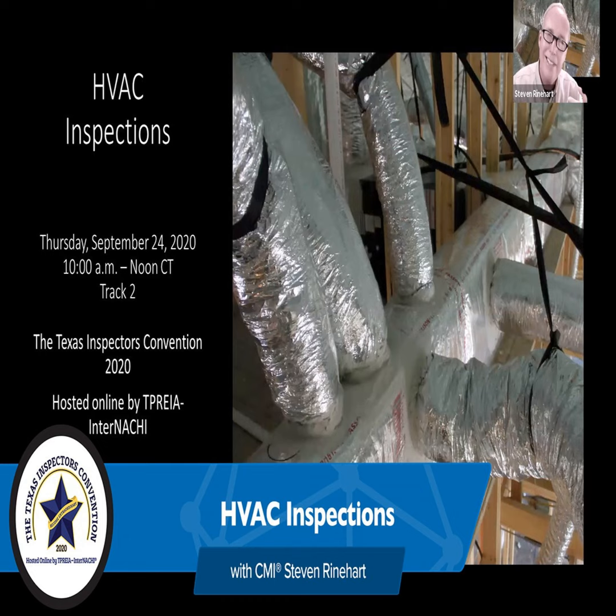Other places have humidity of 30, 40, 50%. Houston may sit at 90% in the morning. You turn on that AC, it's spending a lot of its energy dehumidifying and little energy cooling. You will not see the same cooling performance for the same unit. It's not apples to apples. So a statewide 15, 18 degrees is going to have an issue. We'll address that a little more there.